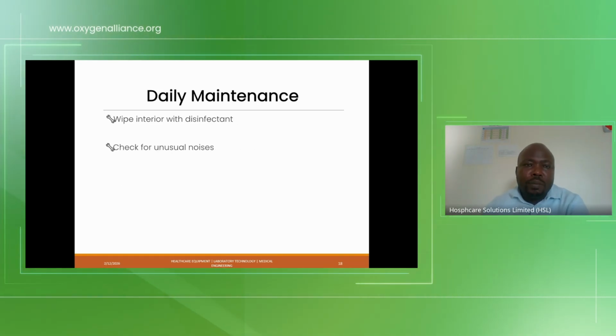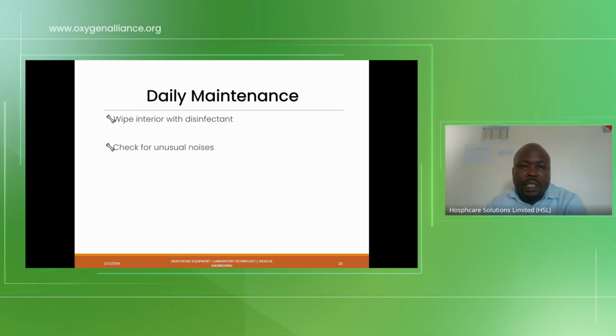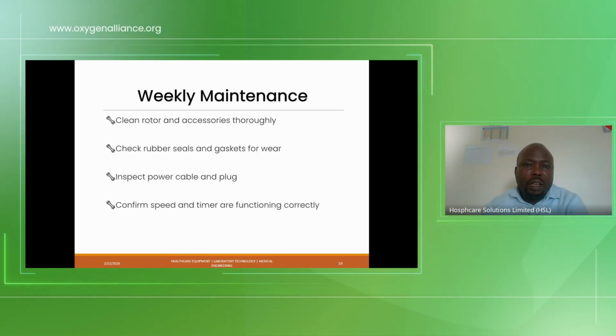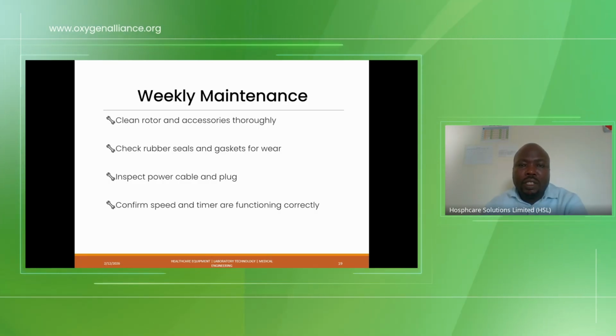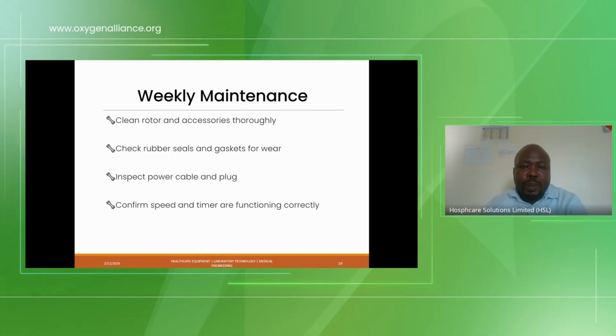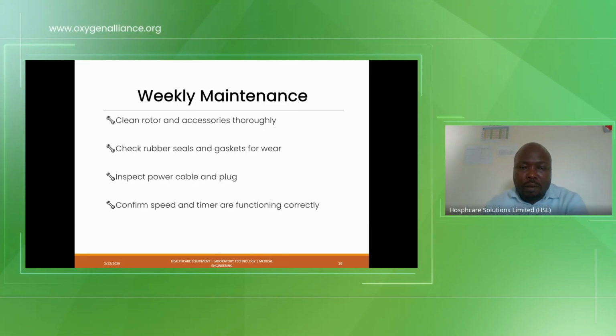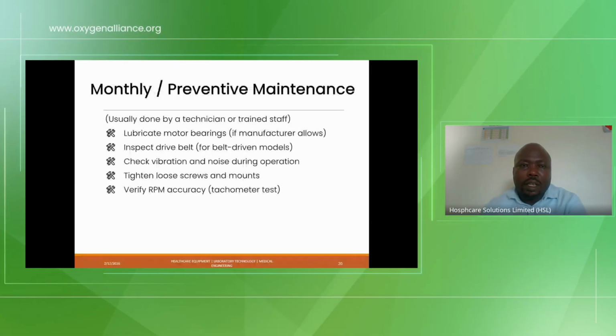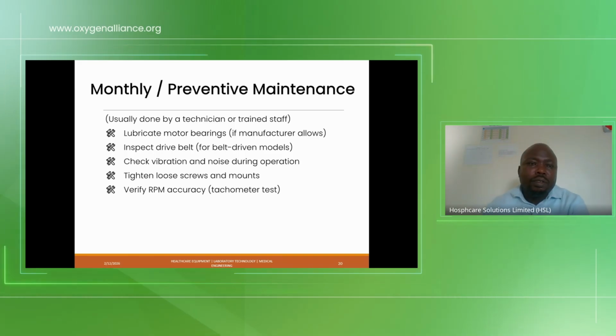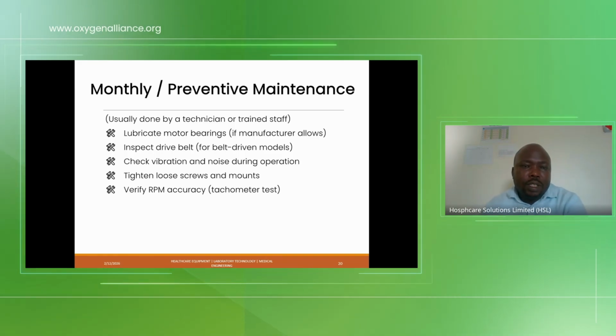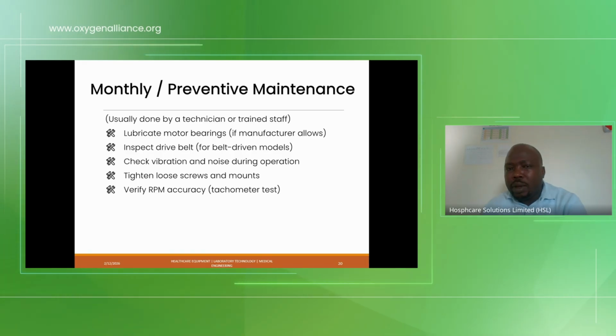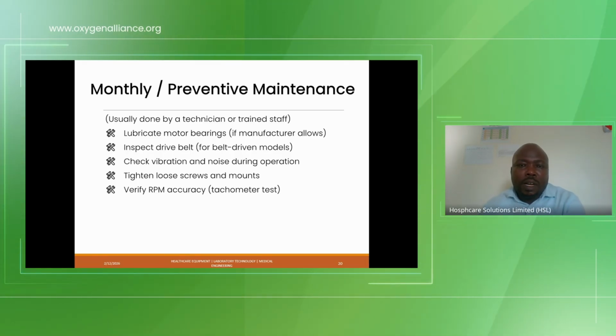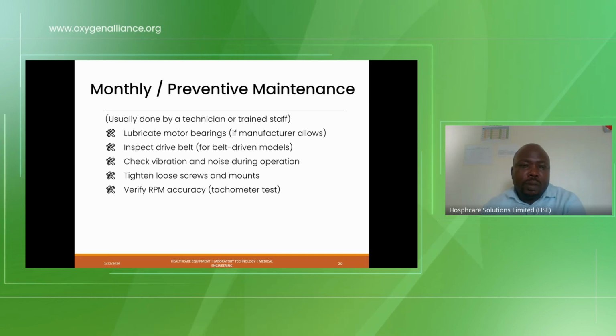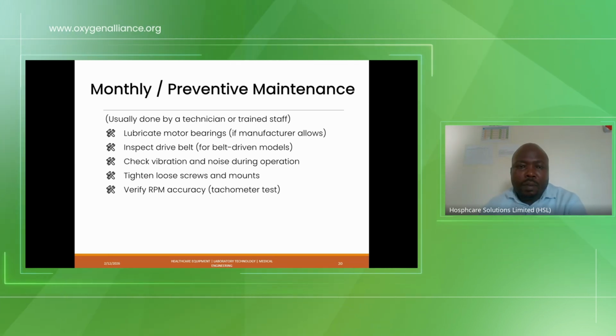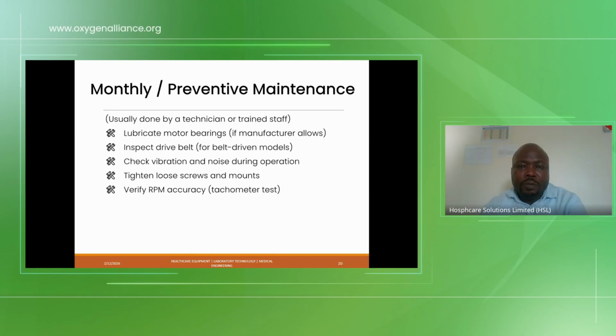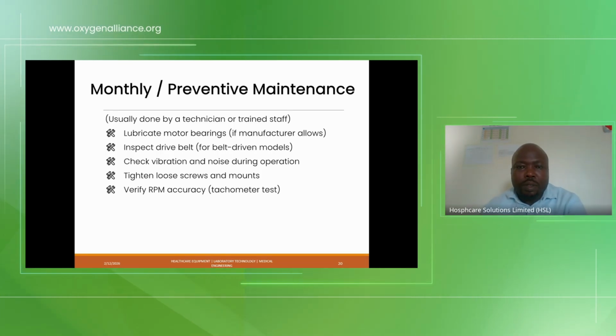Daily maintenance: you wipe the interior with disinfectant and check for unusual noise. Weekly maintenance: clean the rotor and accessories thoroughly, check rubber seals and gaskets for wear and tear, inspect power cables and plugs, and confirm speed and time are functioning correctly. The monthly preventive maintenance is usually done by a technician or trained staff. You need to lubricate motor bearings if the manufacturer allows. Remember, there are some motors you can't lubricate. You inspect the drive belt, and if the belt is still in good working condition, you check vibration and noise during operation.